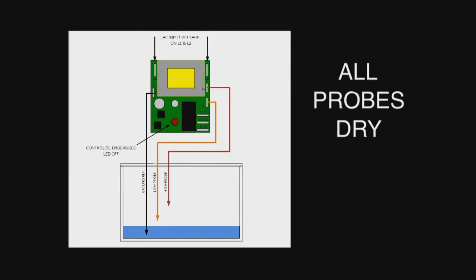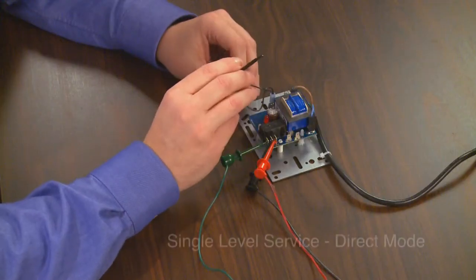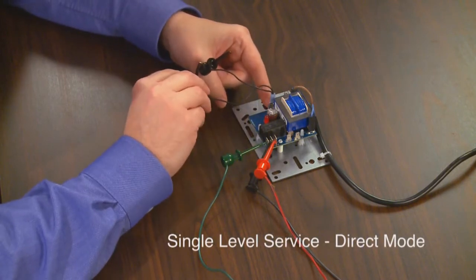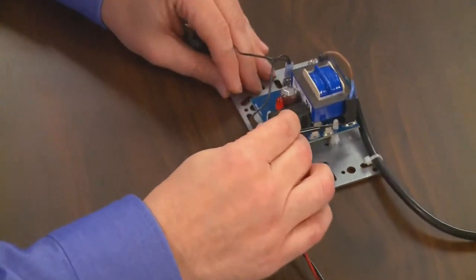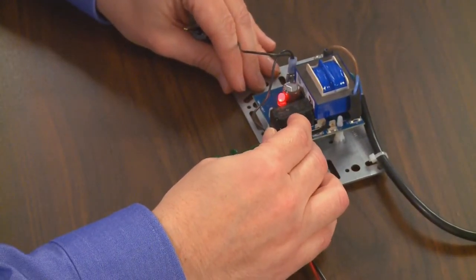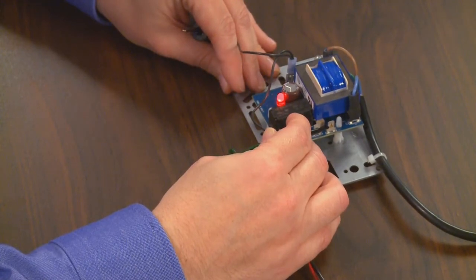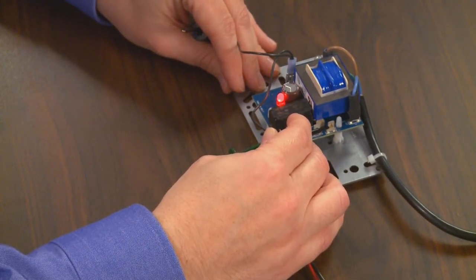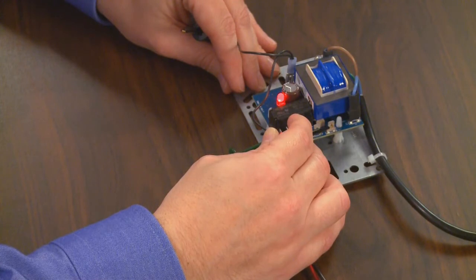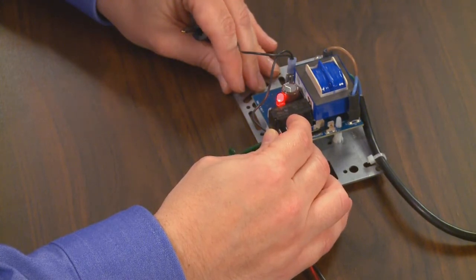Let's first do single level service. We take our jumper from the ground reference probe connection to our high probe connection and as I make that contact the LED came on and the relay is energized simulating that the probe is wet.